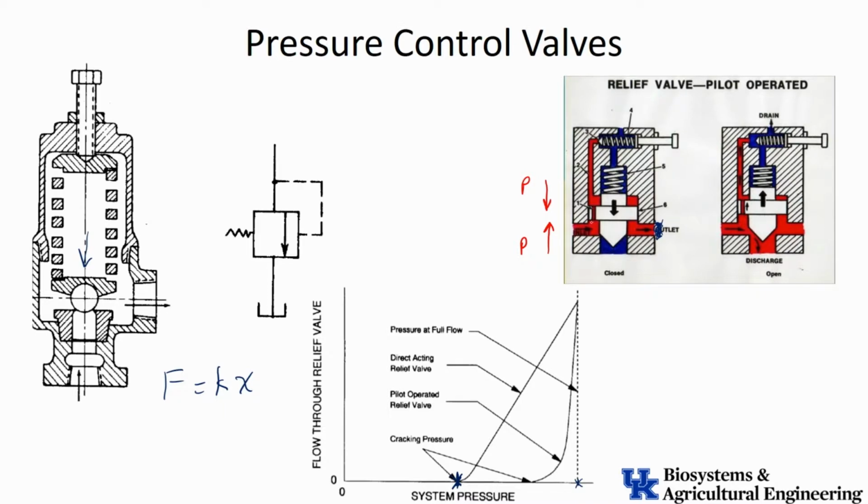They counteract each other. Okay, now in addition, on top we have this spring. So we also have this force of the spring pushing down on that poppet and keeping it closed. Okay, so there's like an extra force up here. This thing isn't going to open. Now, at some point as this pressure increases, the pressure gets higher and higher and higher here. If I look clear up on top, at some point it's going to open this little relief valve here.